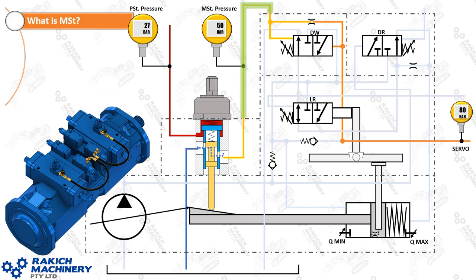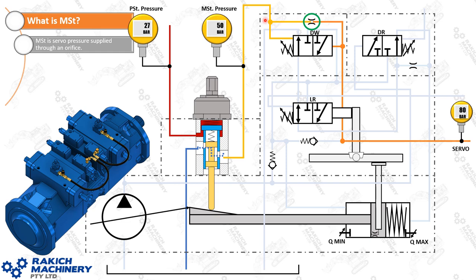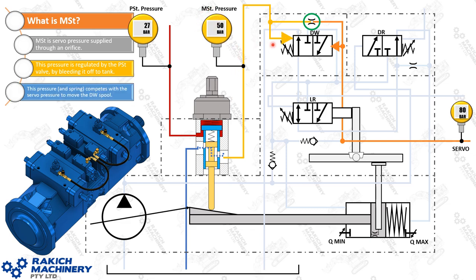What is MST? MST is the gallery on the outside of the pump that goes from the DW valve across to the PST valve — these hoses on the actual pump. It's just an 80 bar servo pressure which is supplied via an orifice, regulated by the PST valve. As that valve opens and closes, this pressure will rise and fall — as it closes off, that pressure will increase. Its main duty is to act with spring tension on the DW valve, competing with the 80 bar servo on the other side of the valve to either move it left or right.